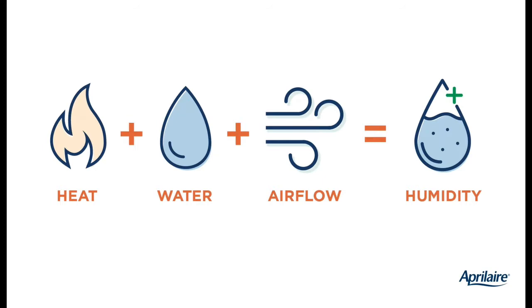Getting good evaporation is a very simple concept. We need three things: water, airflow, and heat. We combine those three things in the right proportions, we're going to get good evaporation — we're going to be able to introduce humidity into the home's air. When you're looking at an application and thinking about whether a steam humidifier installation is going to work, just make sure you'll have sufficient airflow, sufficient water, and you've got the electrical setup generating the heat you need. Troubleshooting, in most cases, is no more difficult than figuring out which of those things we're missing.